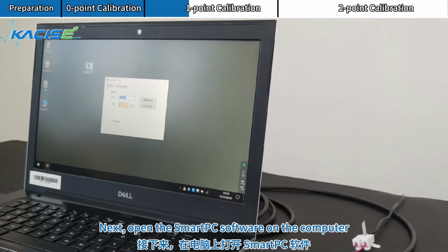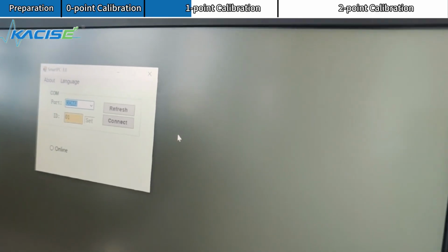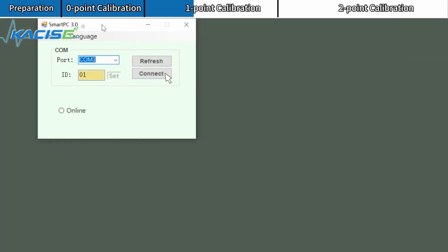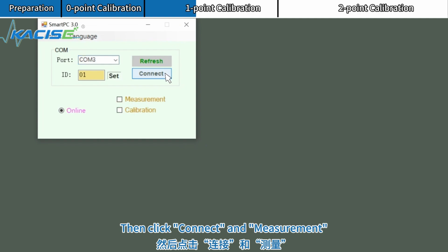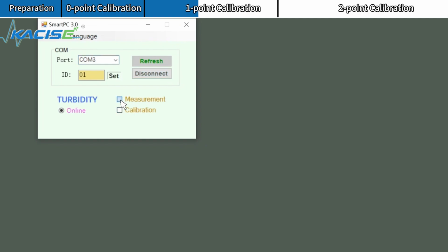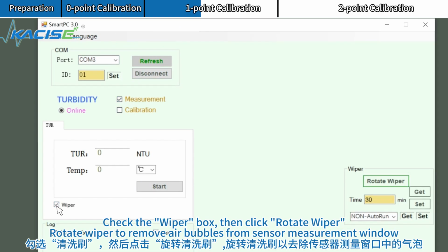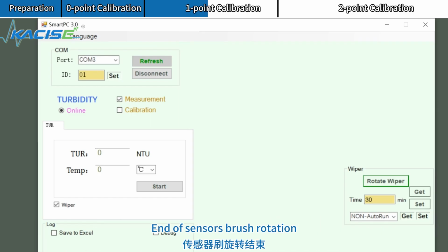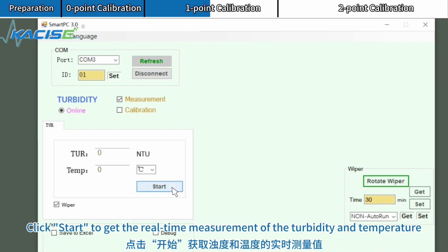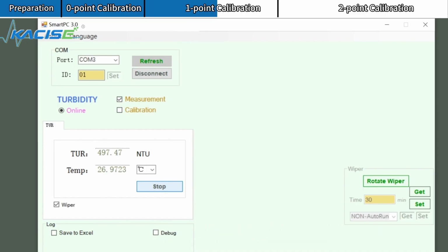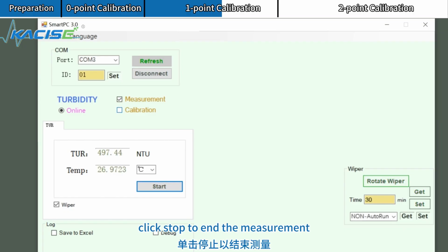Next, open the Smart PC software on the computer. Then click Connect and Measurement. Check the wiper box, then click Rotate Wiper. Rotate wiper to remove air bubbles from sensor measurement window. End of sensor's brush rotation. Click Start to get the real-time measurement of the turbidity and temperature. Click Stop to end the measurement.